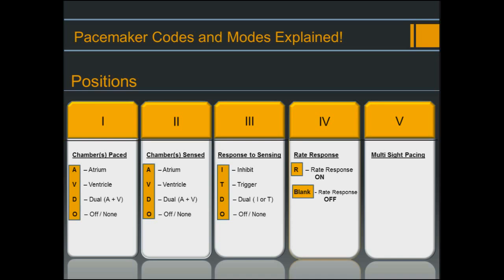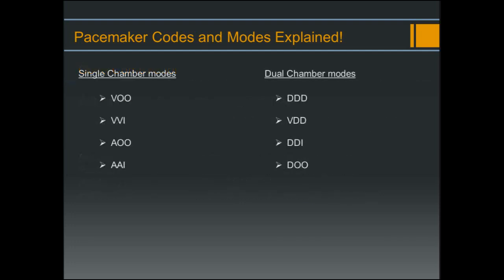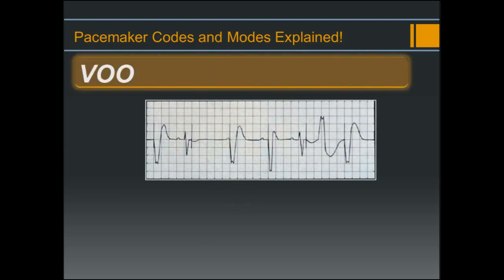To review: each of the positions of the NBG code is assigned a letter, and it is the combination of those letters that describes how the pacemaker will function. Position one is the chamber or chambers being paced, position two is the chamber or chambers being sensed, position three is the response to sensing, and position four is rate response or rate adaptive pacing. From the different letter combinations, the pacemaker has several modes. It's easier if we break those modes up into single chamber modes and dual chamber modes. The single chamber modes are VOO, VVI, AOO, and AAI.